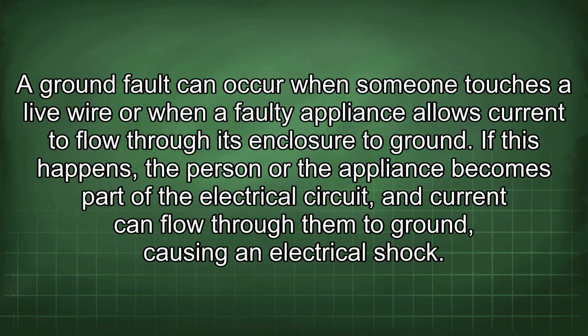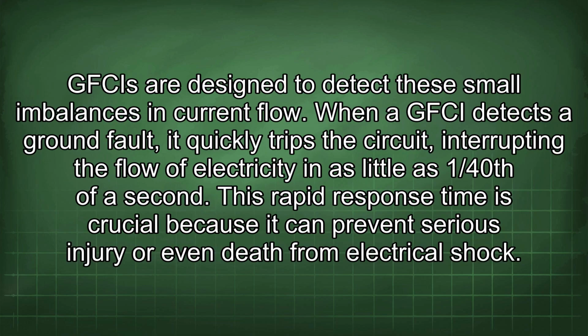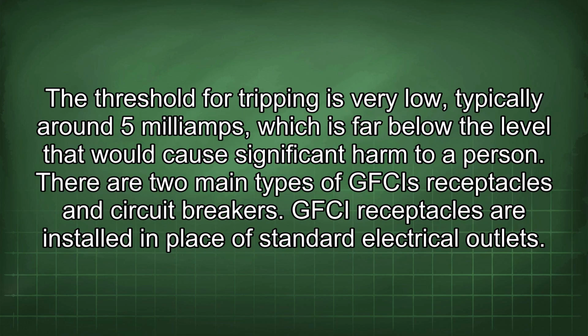A ground fault can occur when someone touches a live wire or when a faulty appliance allows current to flow through its enclosure to ground. If this happens, the person or the appliance becomes part of the electrical circuit, and current can flow through them to ground, causing an electrical shock. GFCIs are designed to detect these small imbalances in current flow. When a GFCI detects a ground fault, it quickly trips the circuit, interrupting the flow of electricity in as little as 1/40th of a second. This rapid response time is crucial because it can prevent serious injury or even death from electrical shock. The threshold for tripping is very low, typically around 5 milliamps, which is far below the level that would cause significant harm to a person.